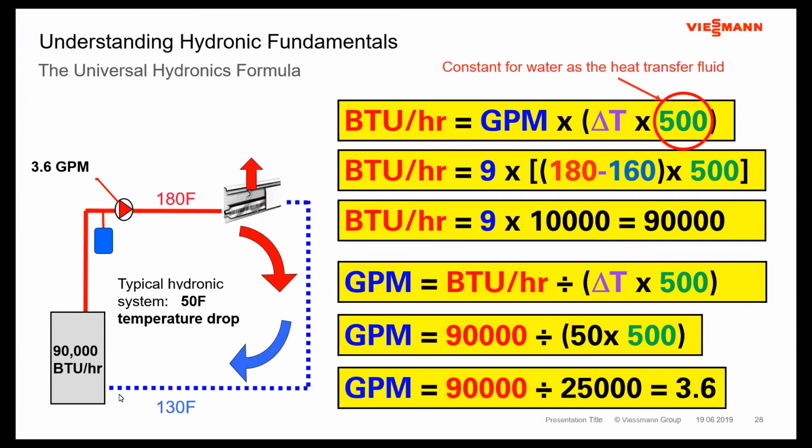and we can start to drive the boiler into a condensing operation, even though we have a high temperature coming out, because again, everything is dictated, as far as condensing, by what's coming back to the boiler on the return side, and of course how it's going to pull that flue gas temperature down enough to get it into dew point.